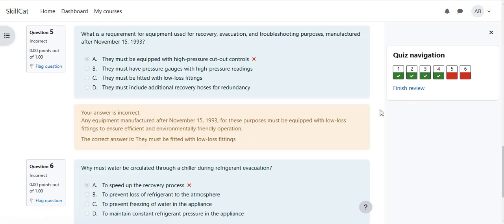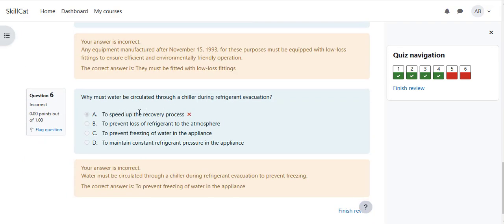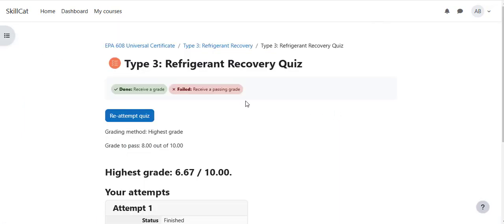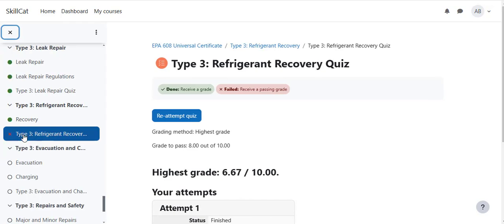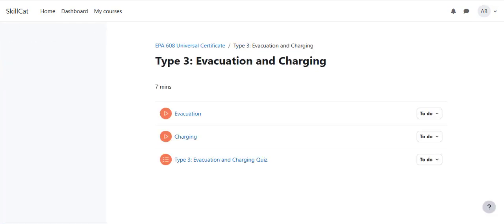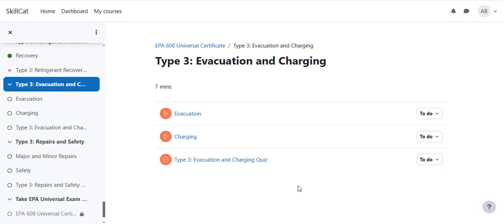Okay, we have 2 questions. Okay, the answer, any equipment manufactured after November 15, 1993, so they must be fitted with low-loss fittings. Lawless fitting, sorry. Why must water be circulated through the chiller during the refrigerant evacuation? To prevent freezing of water. Okay. The next one is evacuation and charging. Let's check evacuation.